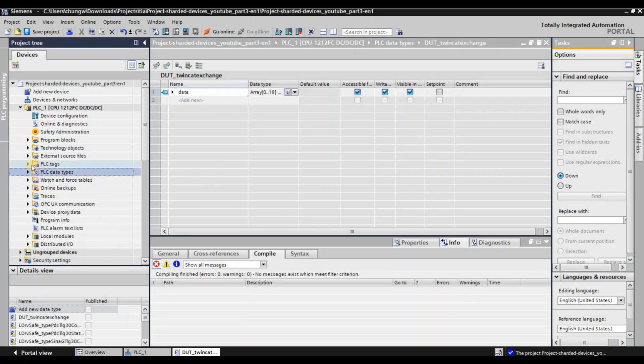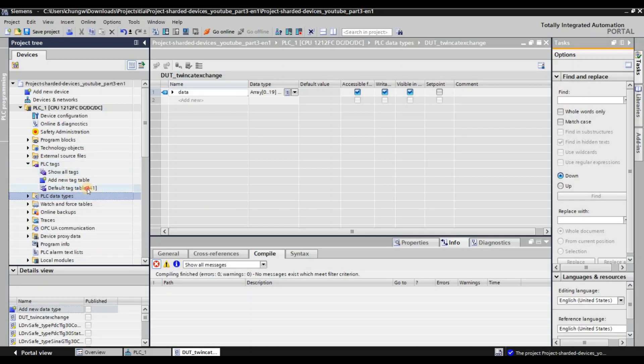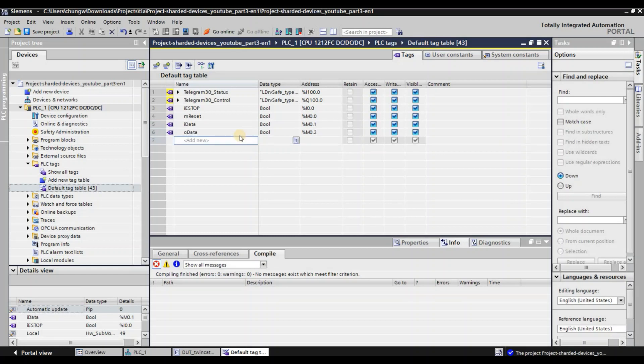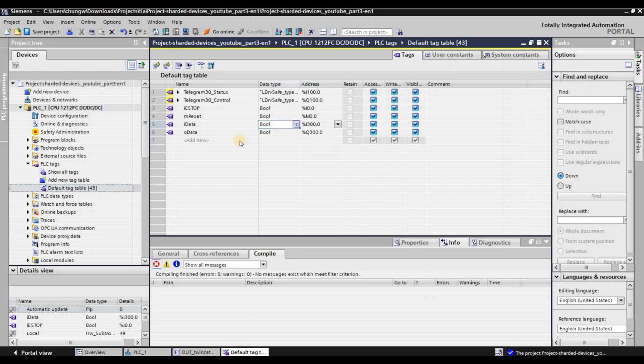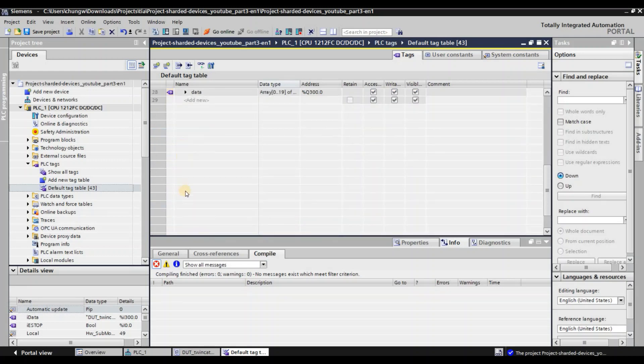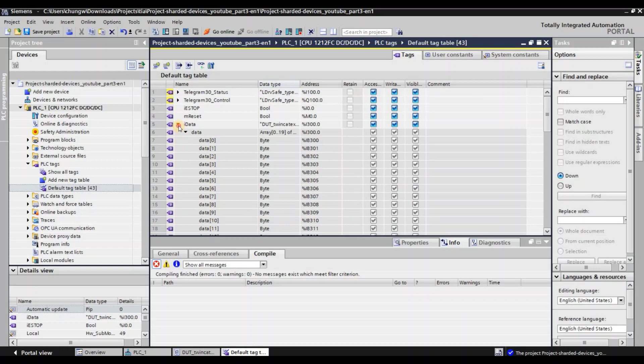Go to PLC tags, go to the tag tables. You can define two variables for input and output. The first one is input — IData, all data, at address %I300.0. It's input. And the last one is %Q300.0, which is output. For the data types, use the data type we defined in the last step. Copy it. Now data is automatically defined — 20 bytes input and 20 bytes output. Very convenient.